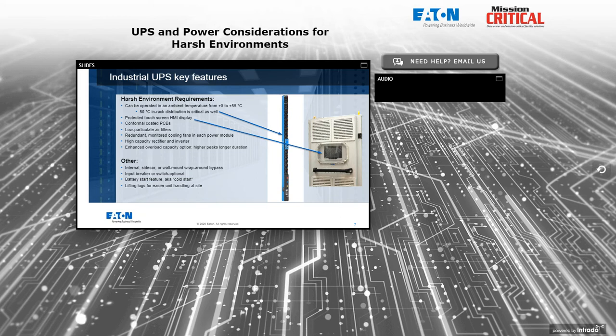Another common feature is a battery start. In other words, the ability to start the inverter on battery without any utility power present, sometimes known as a cold start capability. There are certain industrial applications where it's handy to be able to run the critical load, at least for a short period of time, off the UPS battery, even when incoming utility power is not present.